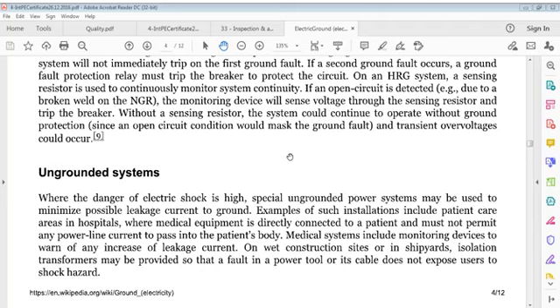Medical systems include monitoring devices to warn of any increase in leakage current. On wet construction sites or in shipyards, isolation transformers may be provided so that a fault in a power tool or its cable does not expose users to shock hazards.